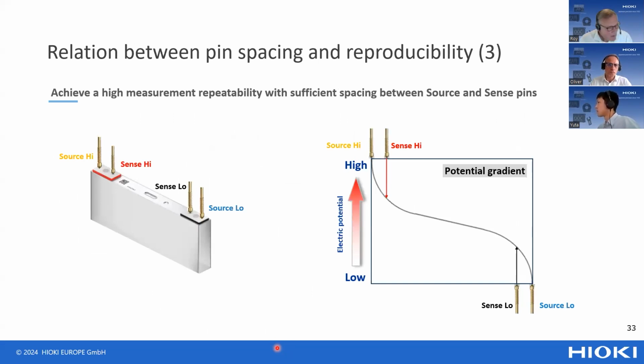We showed this example because it's graphically easy to demonstrate the difference, but in general it's also applicable for cylindrical cells. It's a little bit more different, but the principle is the same. So if there's any possibility to have the probes a little bit further apart, it will improve your repeatability for other types of battery, like pouch or cylindrical cells too. It's not only for prismatic cells.